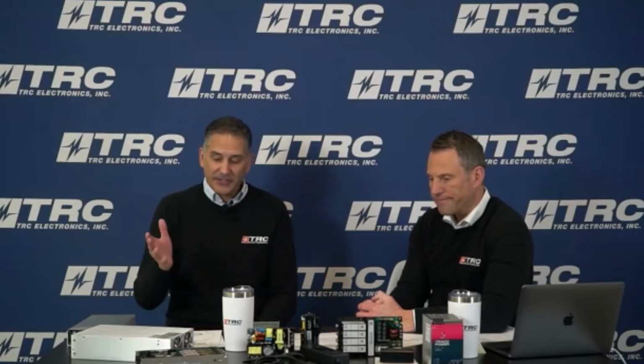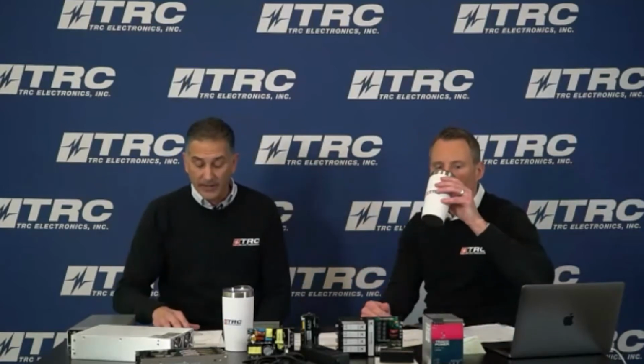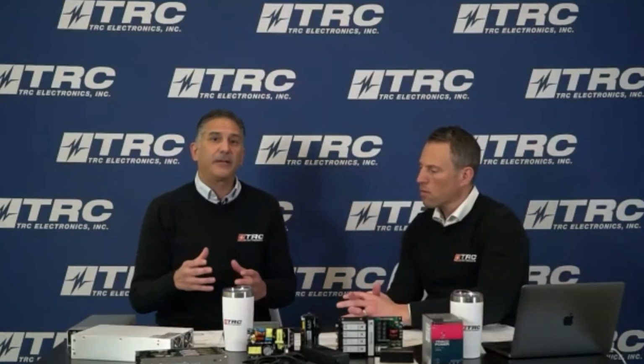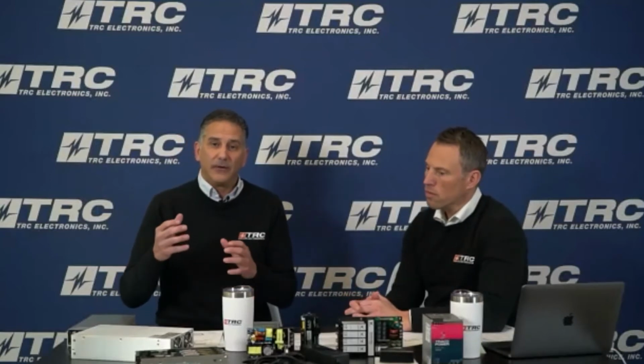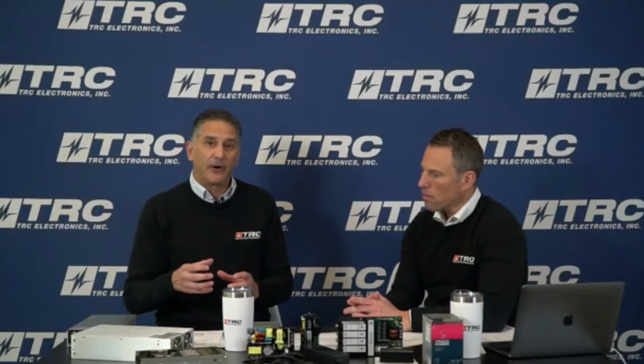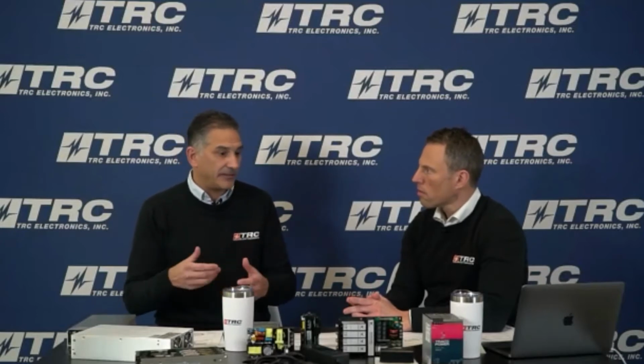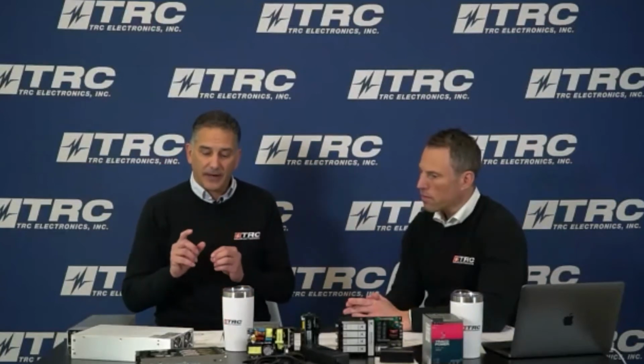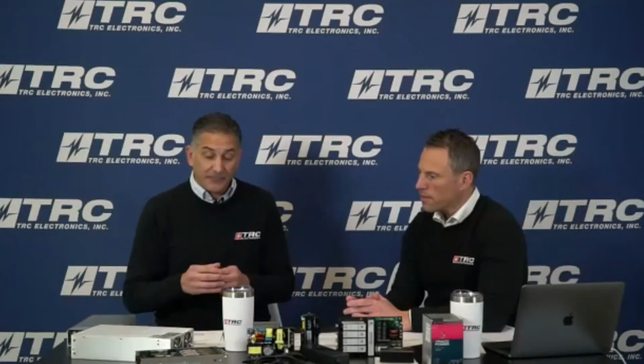Just to give you an example of an experience we had recently, where we realized after the fact that we had an application where we needed conformal coating. What conformal coating does is protect the PC board and components from excessive dust and debris or contaminated environments. But what we didn't realize is that if you don't place the power supply in a specific location to make sure it's free from water that can accumulate inside, you can run into an issue.